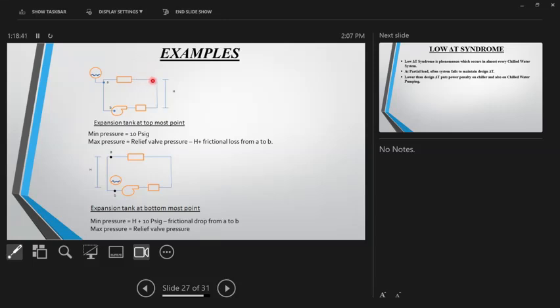So the minimum pressure will always be at the topmost point, correct? My expansion tank is also at the topmost point. So the minimum pressure in the expansion tank is also 10 psig. 10 psig all over here is good. So my expansion tank minimum pressure was also 10 psig.